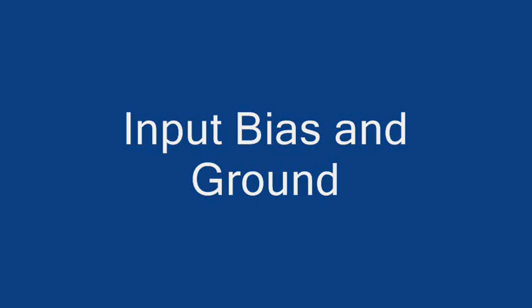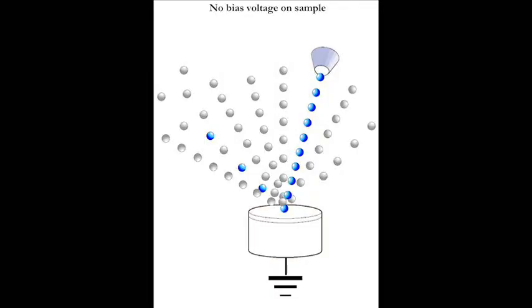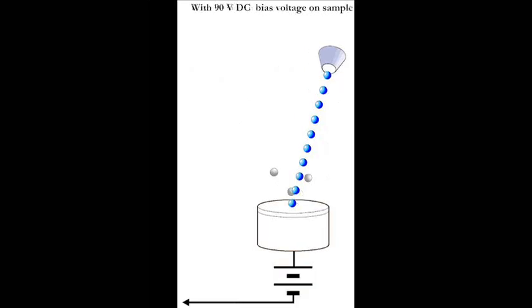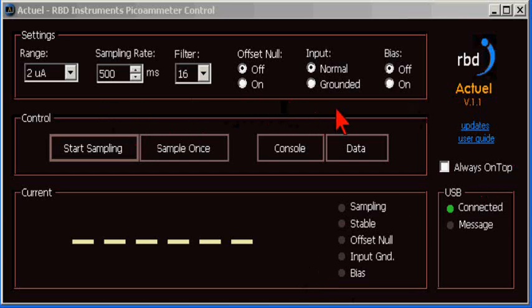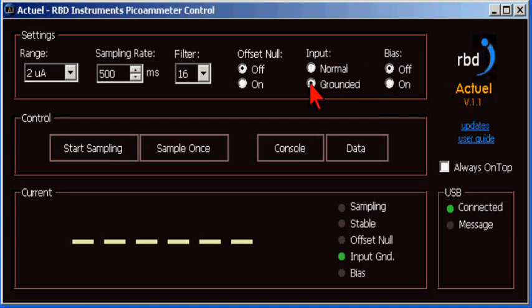When measuring current on a target in a vacuum system, secondary electrons are generated, which affect the accuracy of the measurement. By applying a 90 volt bias to the target, the number of secondary electrons produced is substantially reduced, which gives you a much more accurate measurement. Let's ground the input and select the bias.